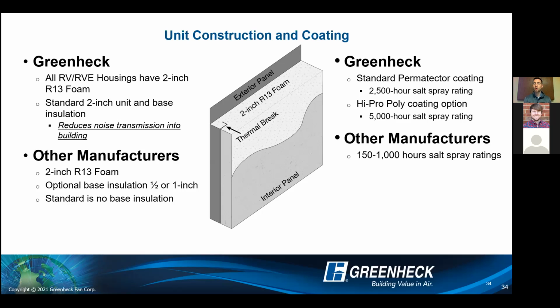And then from a coating standpoint, our standard coating is a 2,500 hour salt spray rating. That's that nice Permatector coating. Again, standard on all RVEs. If you do have those situations where you need to increase that salt spray rating, we go up to 5,000 hours with our HiPro Poly coating. We can also do some color match options on that one as well. Generally, what you're seeing from other manufacturers is 150 to around 1,000 hour salt spray rating as standard.